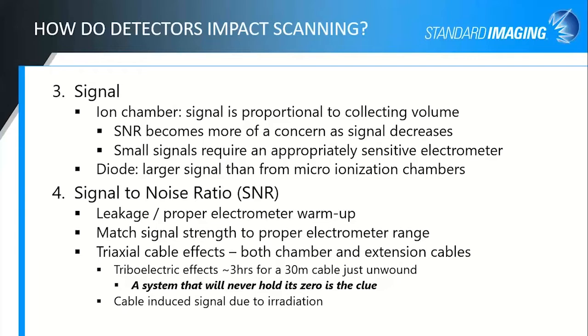Signal to noise ratio, I mentioned already, is important. If you have electrometer leakage, or if you haven't properly warmed up your electrometer, you could have issues with the signal to noise ratio. It's also important, if you can choose an electrometer range for scanning, to choose the appropriate range that matches the signal that you would expect to get from your detector. Be aware that you need to consider the in-field signal level. If you're in the high range for the in-field signal level, you may not get as good results over in the tails if you're bumping down against the low end of that high range. There can be triaxial cable effects. This again matters a little bit more for your point measurements if you're unwinding a really long cable, but there are some triaxial cable effects that can affect your SNR and your minimum measurement current as well.